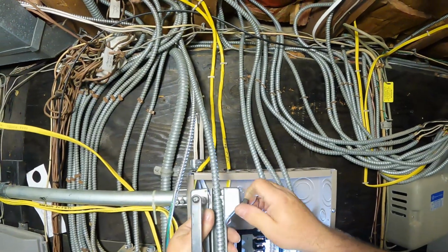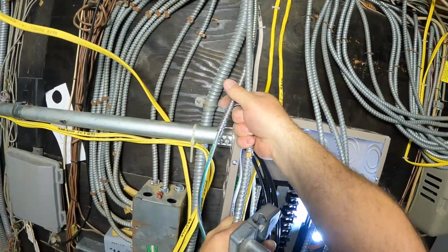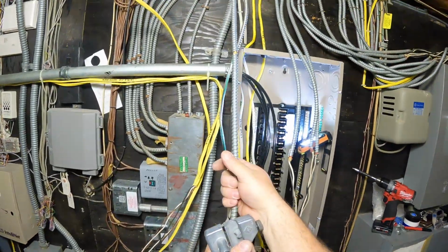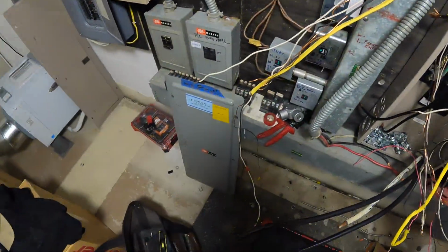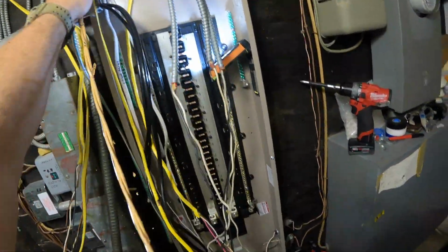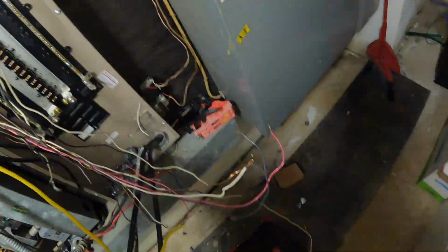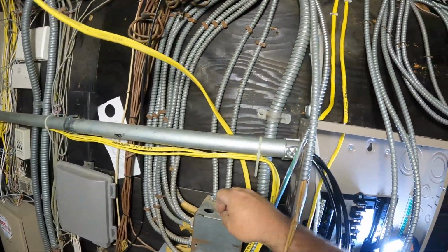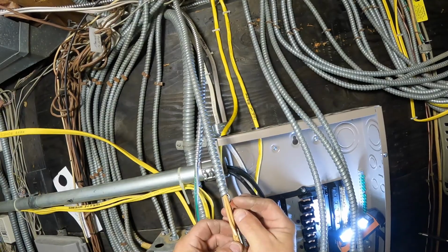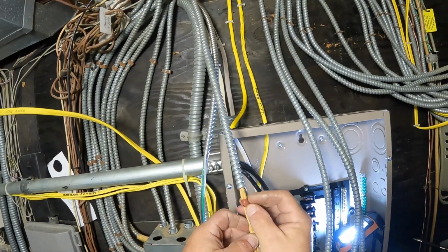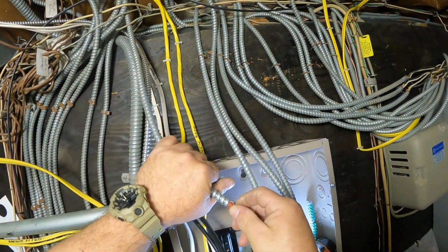And what you do is you feed that in, you tighten down that knob. It cuts the BX to an area just enough to break the sheathing away from the conductor without nicking the conductor. And I highly suggest you get one of these if you're going to be doing a lot of this work. Sure, with the MC cable, you could use a pair of diagonal cutters, or we call them dikes in the field. But that's definitely not advisable.